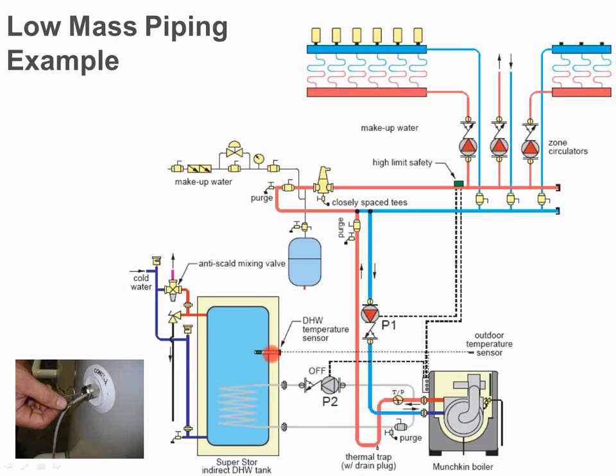Once that sensor is satisfied, it says, okay, I'm done. Normally there's a post-purge that would take whatever heat's left in that boiler and dump it into that tank, so it's not getting wasted. And then we'll go back and turn on our heating system if it's needed. If not, the boiler just goes down into shutdown mode. Okay? But basically P1 will be turned on. Whenever we're dealing with these two temperatures and that kind of stuff, we'd like to always post-purge and dump whatever water we have either into the heating system or the indirect. Don't leave it in the boiler.